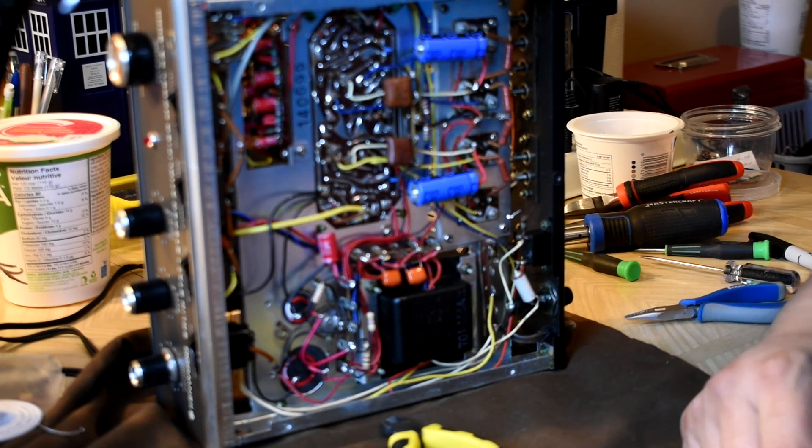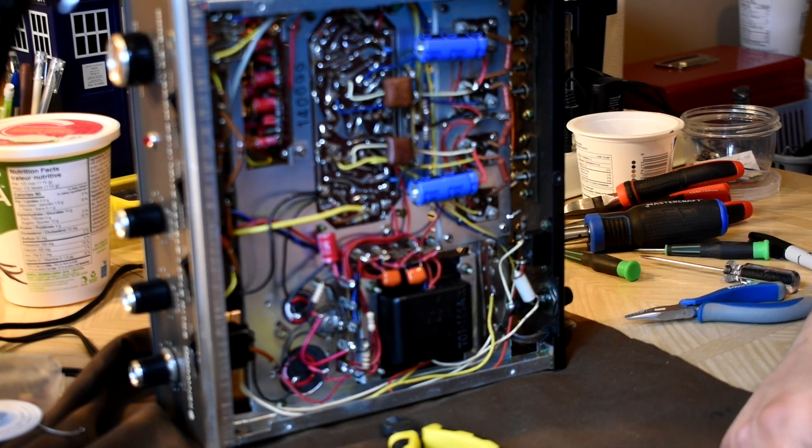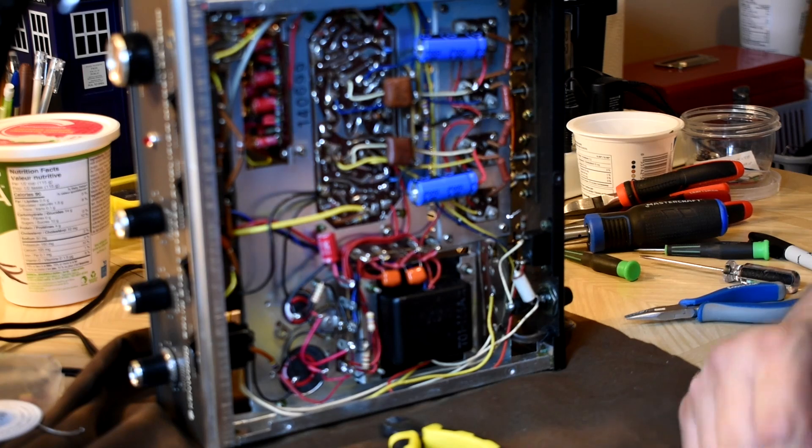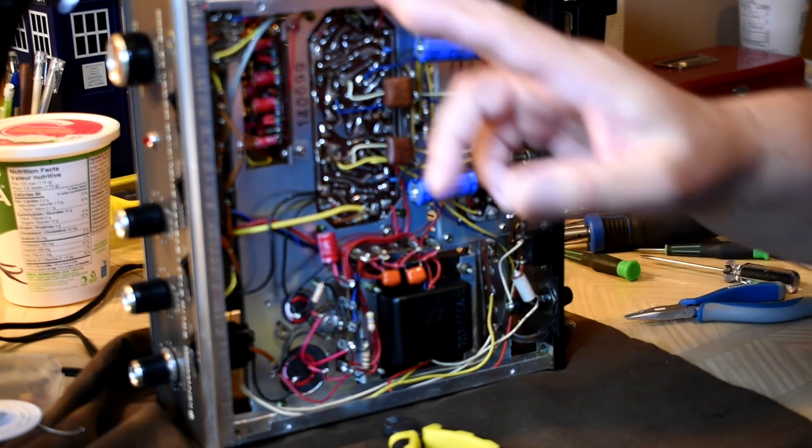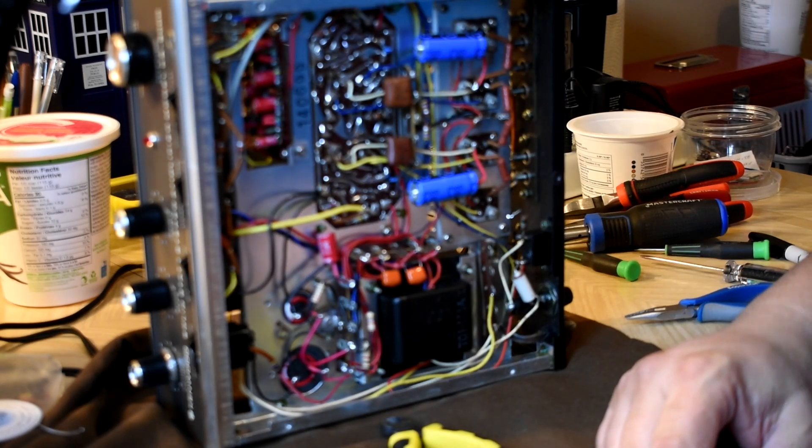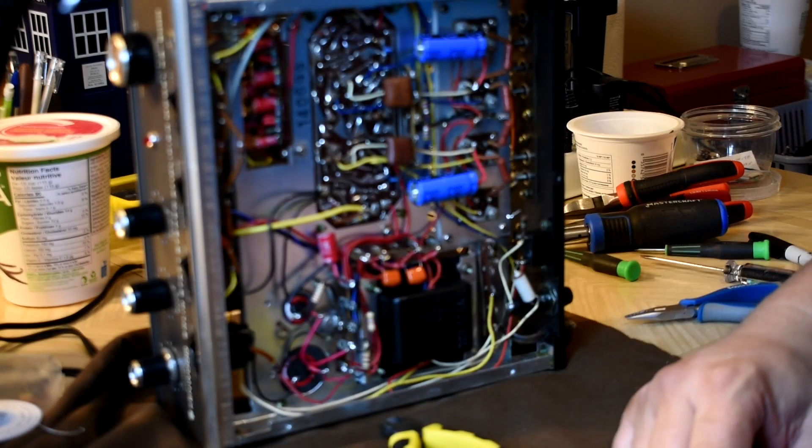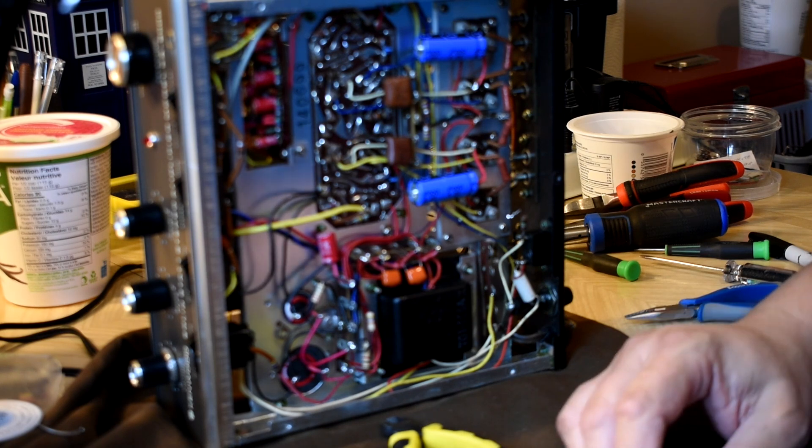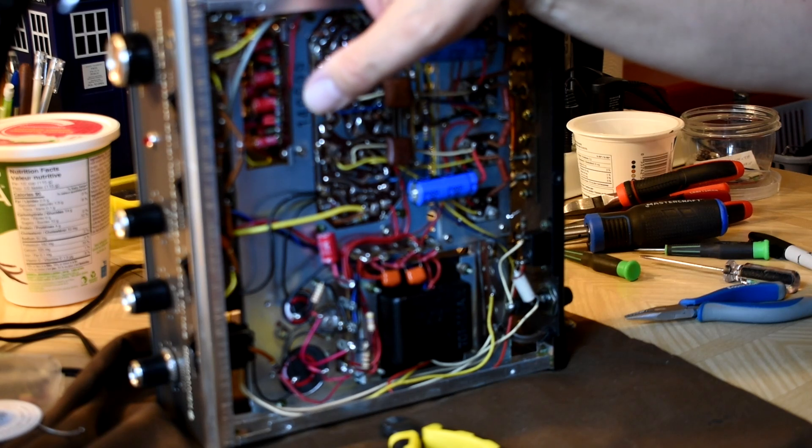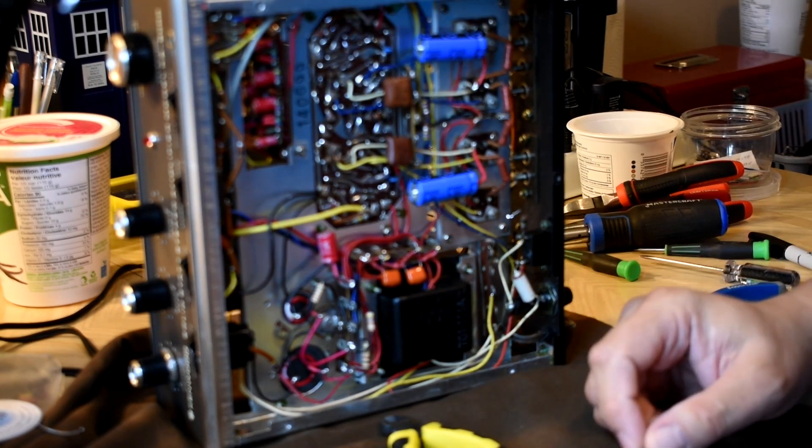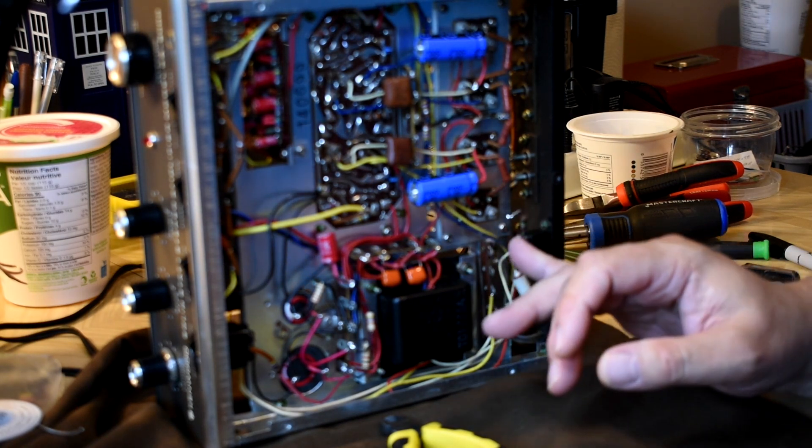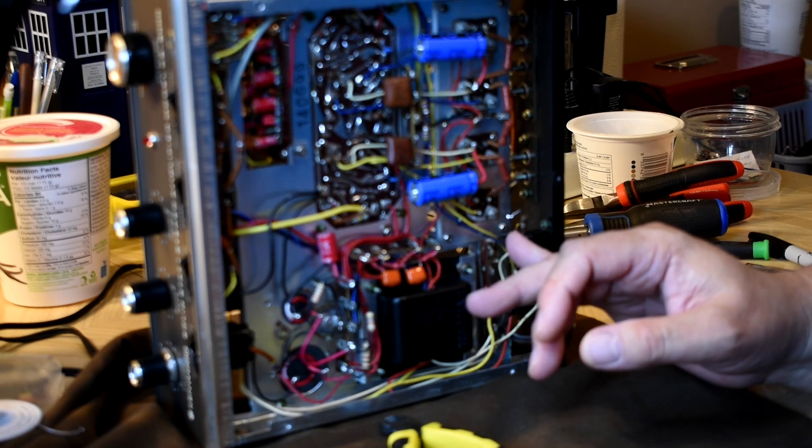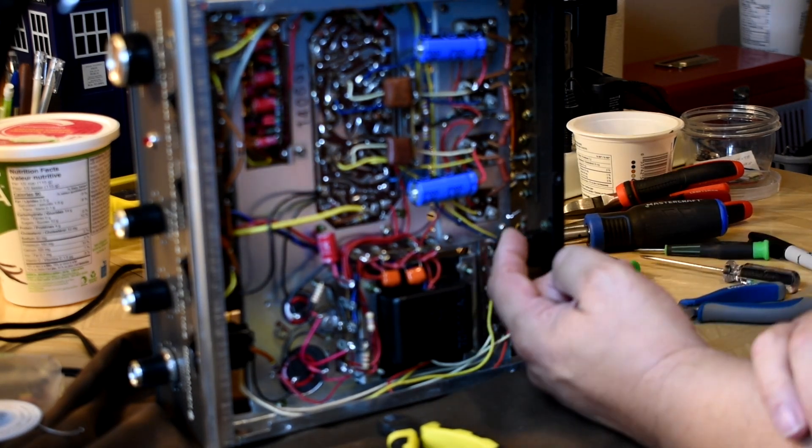I remember one time going to a place where they had dances, that kind of stuff, a hall. And the story was they had put in the system and people were getting shocks off of the front panels of the amp and the cassette deck. And so I was sent out there to see what's going on. So I took my meter and I found the front panel had 120 volts between there and ground.